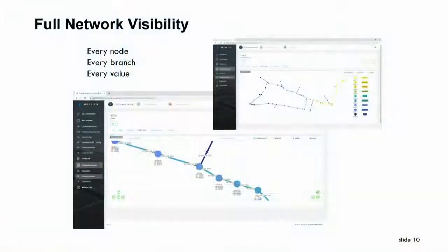So although here we use it on the MV side, for the distribution transformers you get the LV side as well in 4-wire representation, and you can apply that to low voltage networks too, including neutral displacement, multiple earthings, and so on. Once the estimation has run, it's almost as if you had measured everything throughout the network, mapping the available data and measurements into virtual measurements of any operational parameter you could possibly measure.